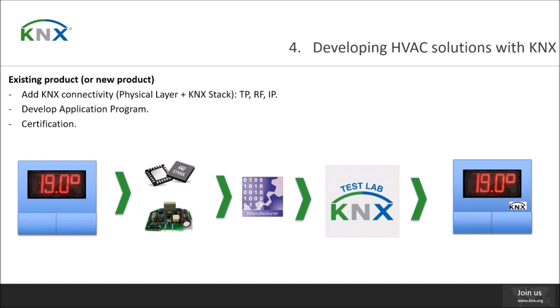Your application program is the key for the well-known interoperability and smooth integration of KNX devices, whatever the brand they are. You need to develop the application program using the manufacturer tool. Lastly, you can initiate your certification process by registering the device at the KNX Association. After that, you can approach any test lab and pursue a positive result in the certification test. Then you achieve the certified status for your device.